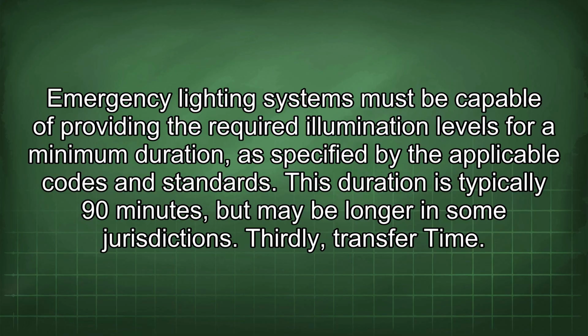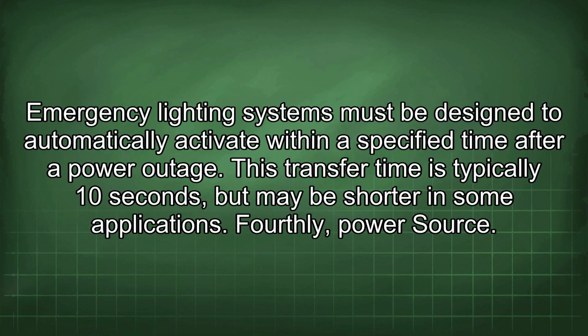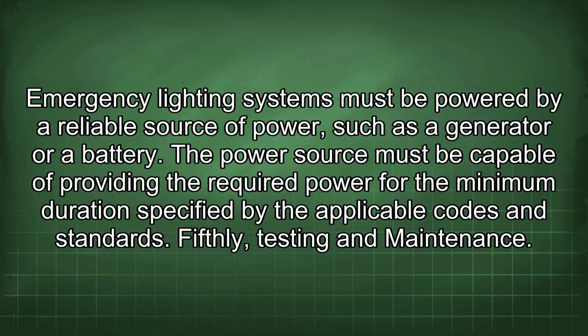Thirdly, transfer time. Emergency lighting systems must be designed to automatically activate within a specified time after a power outage. This transfer time is typically 10 seconds, but may be shorter in some applications. Fourthly, power source. Emergency lighting systems must be powered by a reliable source of power, such as a generator or a battery. The power source must be capable of providing the required power for the minimum duration specified by the applicable codes and standards.